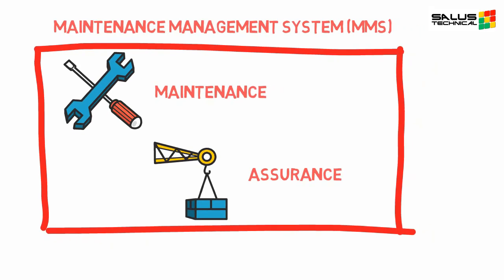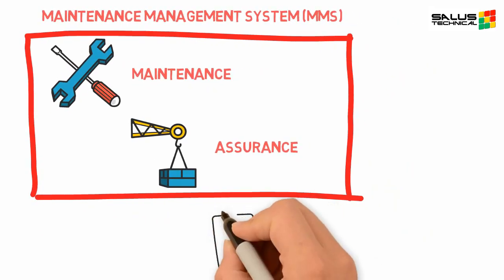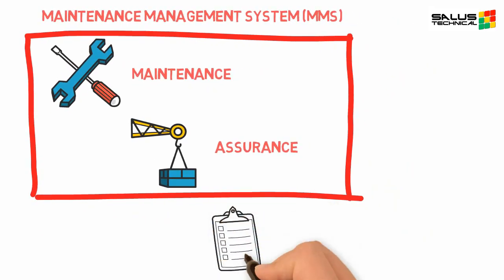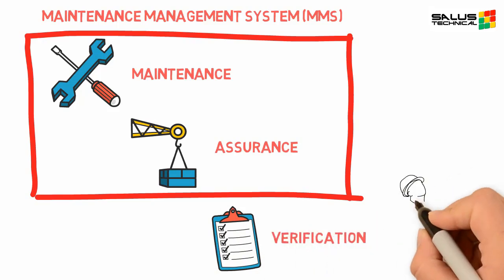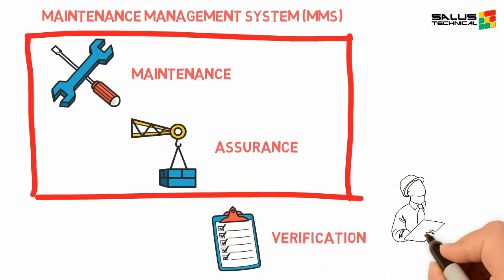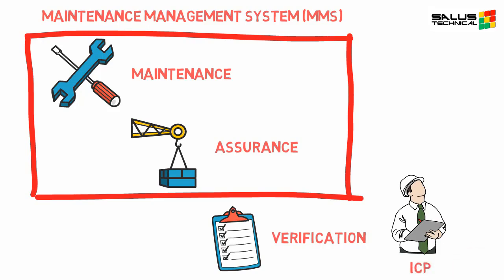There is a further legal requirement within the safety case regulations to have the maintenance and assurance of SECIs verified by an independent, competent person, commonly referred to as the ICP or simply the verifier. It's the operator or the duty holder that carries out maintenance and assurance, whilst it's the ICP that carries out verification.